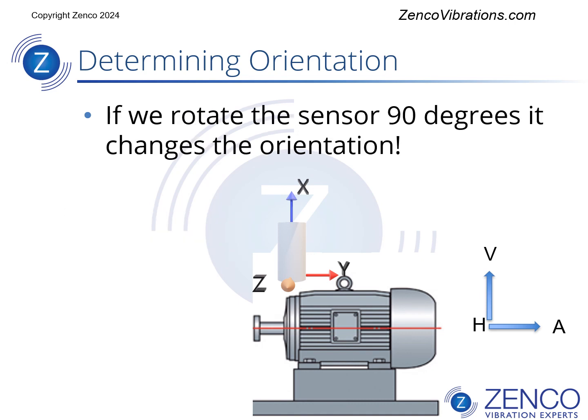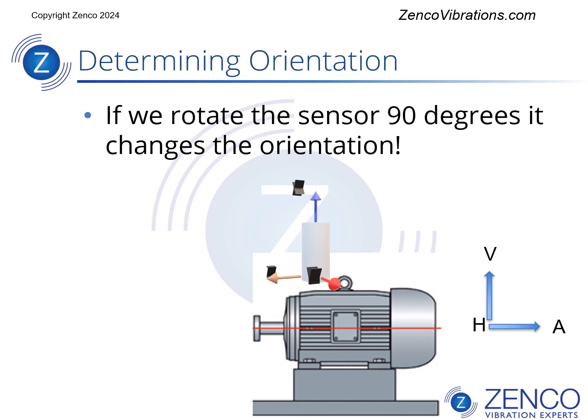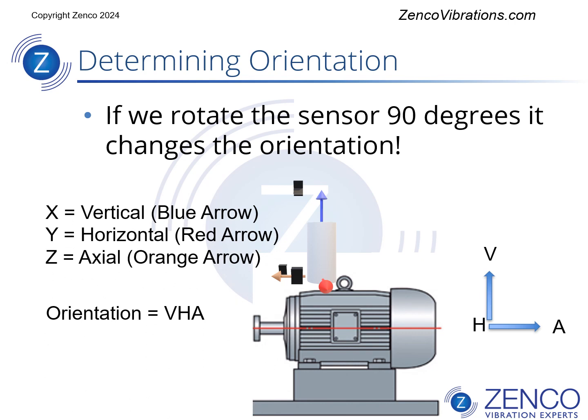If we rotate the sensor 90 degrees, it changes the orientation of the Y and Z axes. The X is still vertical, but now the Y is horizontal — the red arrow — and the Z is axial — the orange arrow. So we would call this orientation VHA.